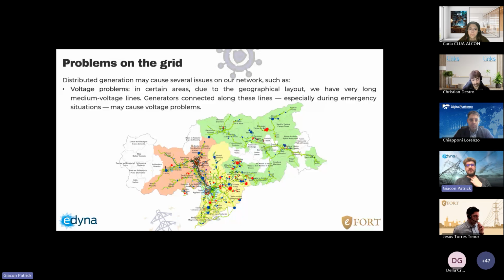One of the main issues we face is related to voltage regulation. In some areas, because of the geographical layout, medium voltage lines can be very long, and when generators are connected along these lines, especially during emergency conditions, they may cause significant voltage problems. In this figure, the red areas represent over voltage conditions, and the blue areas represent under voltage conditions.